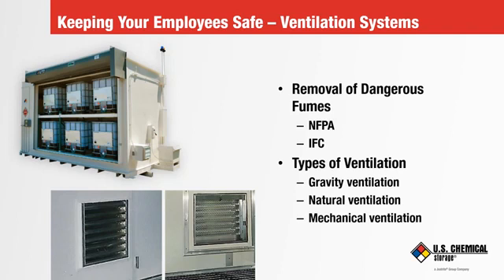The International Fire Code, paragraph 2704.3 says, the fan is to run continuously, have a break glass shut-off switch, and an exhaust vent located within 12 inches of the elevated floor. The exhaust air shall not be recirculated back into the room. In addition, it is important to know how the exhausted fumes mix with the outside air. NFPA also says the fume discharge shall terminate above the roof.